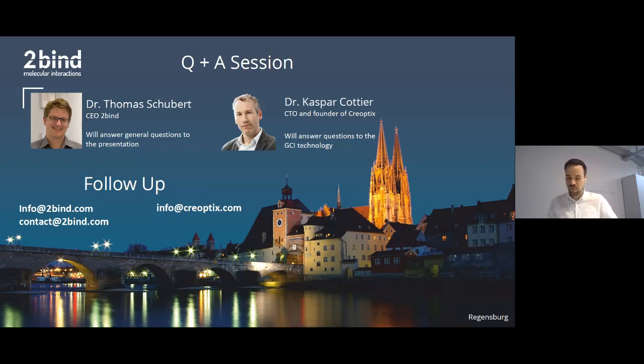First of all, we do have wizards that guide you to selecting the right concentration. This really depends on the window of kinetics that you're interested in. Are you interested in weak binders? Then you obviously have to select a higher concentration. Tighter binders you will measure with lower concentration, and not only concentration but also the timing of your pulses will change. For this we have the wizards guiding you, and as a rule of thumb, you can use the concentration that you would use in a traditional multi-cycle kinetics experiment for determining a certain affinity, which is in the order of 10 times the expected affinity as a concentration to be injected.